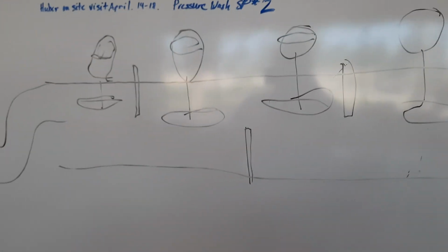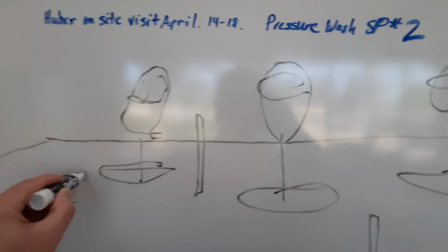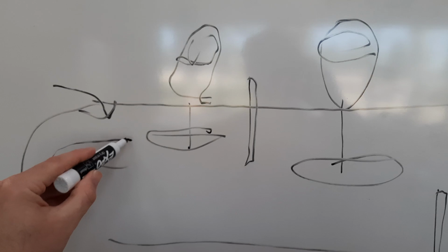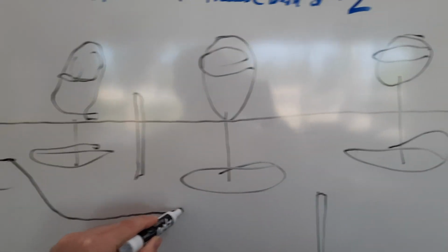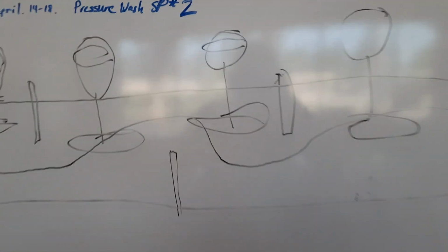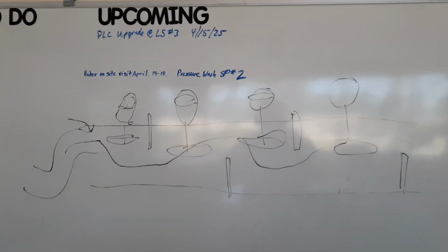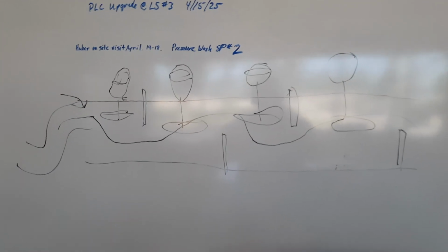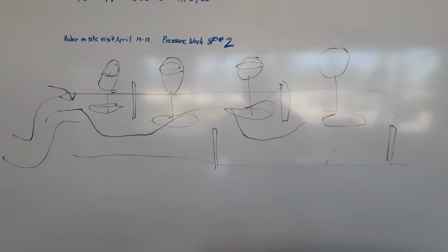Alright, so here's what's going on inside these cells. So the process comes in, liquid oxygen is injected into the process, and it flows through these baffles in the pattern kind of like that. Basically slows it down. Each of these 4 mixers is mixing at a different speed, and that's to make sure that we don't get anything that will get stopped up. And it makes sure that the liquid oxygen is getting to the appropriate bugs to clean the wastewater.